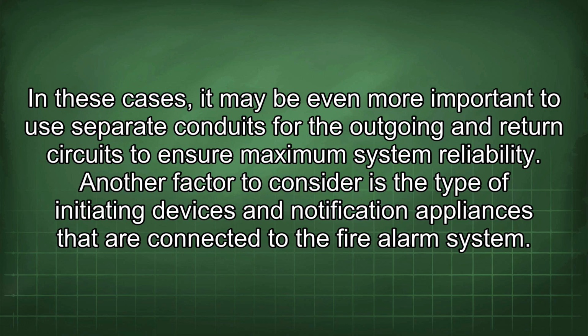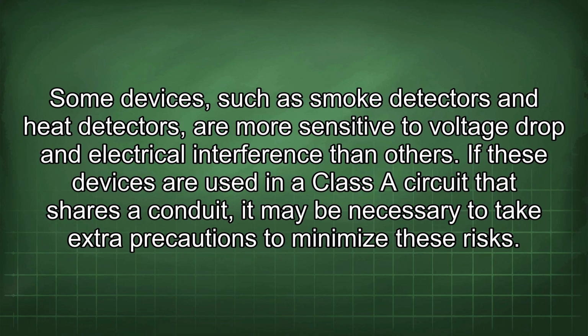Another factor to consider is the type of initiating devices and notification appliances that are connected to the fire alarm system. Some devices, such as smoke detectors and heat detectors, are more sensitive to voltage drop and electrical interference than others. If these devices are used in a Class A circuit that shares a conduit, it may be necessary to take extra precautions to minimize these risks.